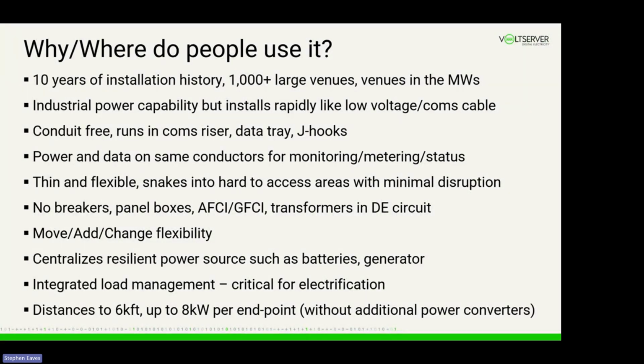Sending it in packet energy transfer format allows it to be qualified as a limited power source technology. Under the National Electric Code, it can use those practices, so there are no breakers or panel boxes, AFCIs or GFIs, or transformers in the DE circuit. Once you convert to digital electricity, it's one communication line from point to point, from the basement of the building all the way up to the apartment.